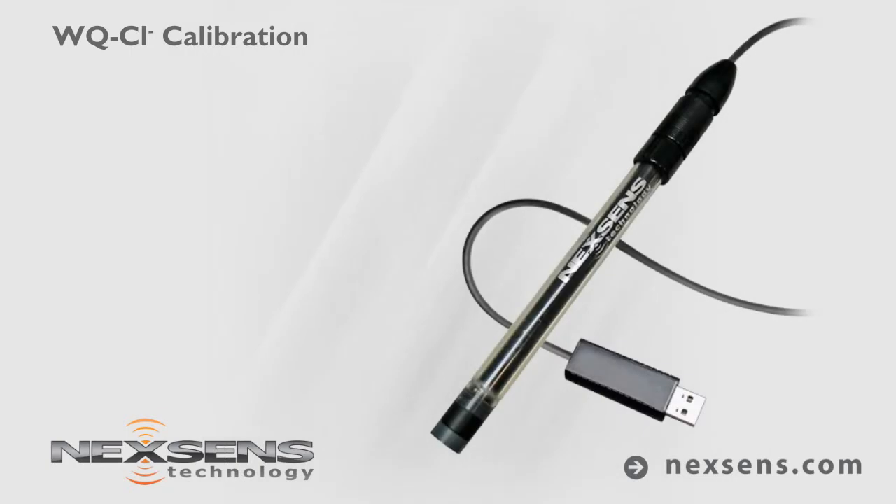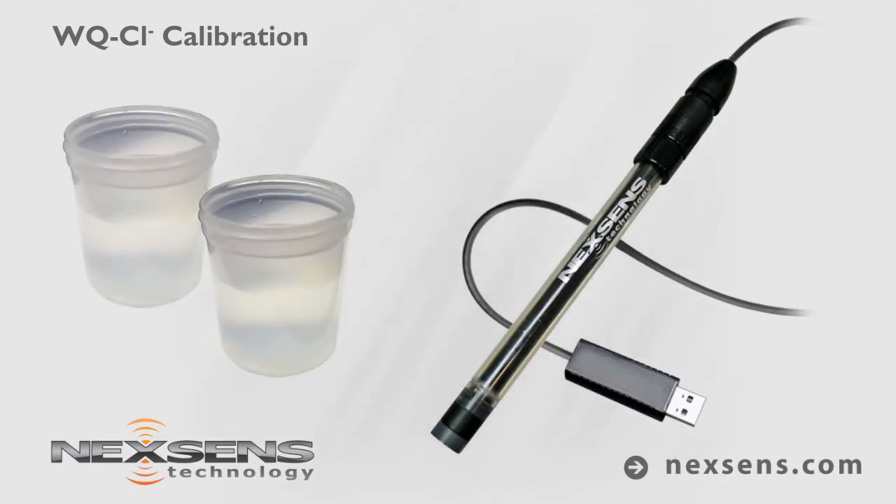Calibration and measurements with the NexSens WQ Chloride sensor are quick, easy, and reliable. The software supports a two-point calibration, which is typically performed above and below the expected measurement range. For this demonstration, the sensor will be calibrated using 10 and 100 parts per million standards.